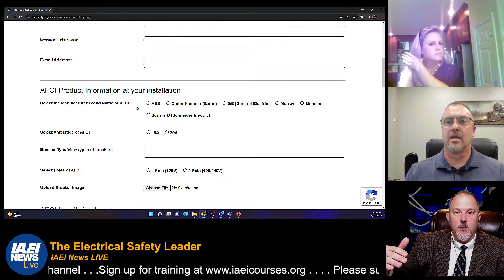I always tell people, if you're troubleshooting these circuits, don't spend a lot of time before contacting the manufacturer. For example, I had a problem in my own house—a GFCI circuit breaker that was tripping on a living room circuit, and I didn't know what was going on. So we talked to my electrician, who contacted my guy back at headquarters, and he gave some ideas on how to break the circuit up. We ended up finding the problem: a stripped conductor that went from inside to an outside receptacle. But the techniques for troubleshooting vary—some people may not be as good at it as others.